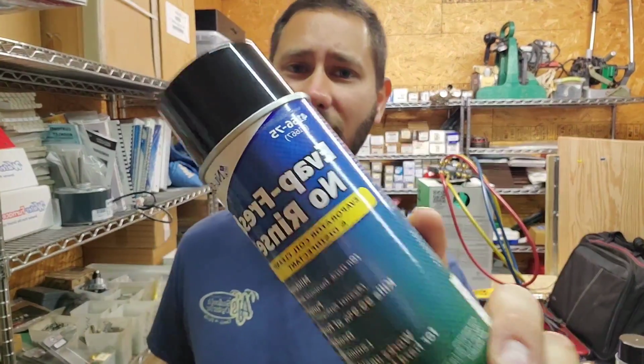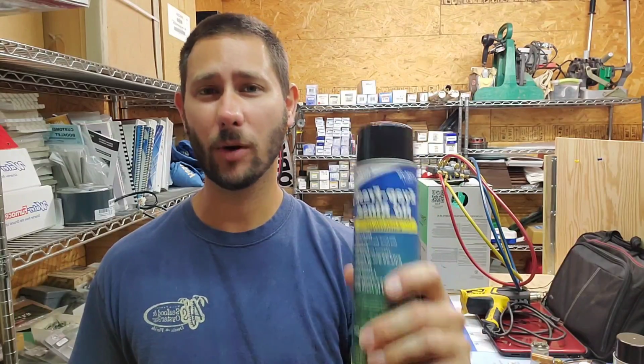Dirty evaporator coils cause the unit to freeze up. Why? Because it causes low airflow. If you have a dirty evaporator coil like this one, then you may need to get it cleaned. I don't recommend cleaning it yourself if you're not a professional, but if you'd like to, make sure you get some no-rinse evaporator coil cleaner. This right here is evaporator coil cleaner, and it's wonderful because you can spray it on the evaporator and it's self-rinsing. If your coil is really dirty, then you may need to take more progressive measures to make sure that you clean it properly.